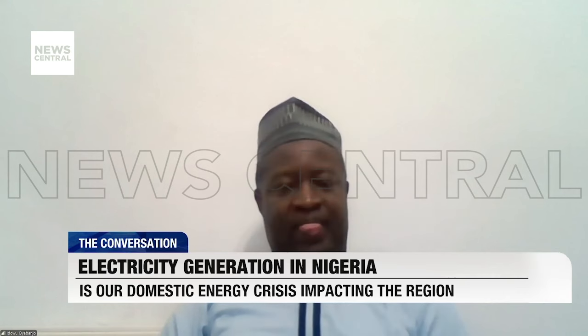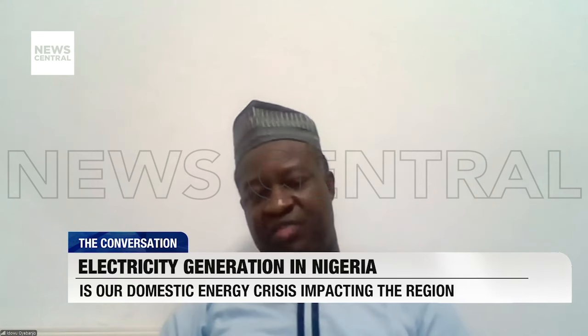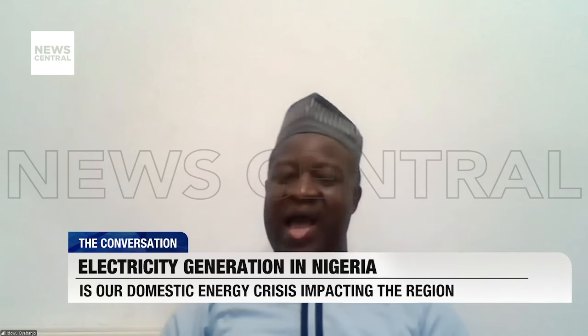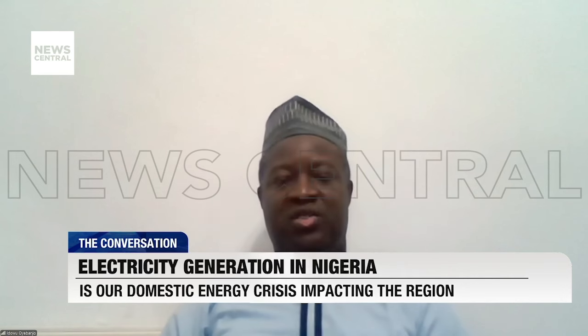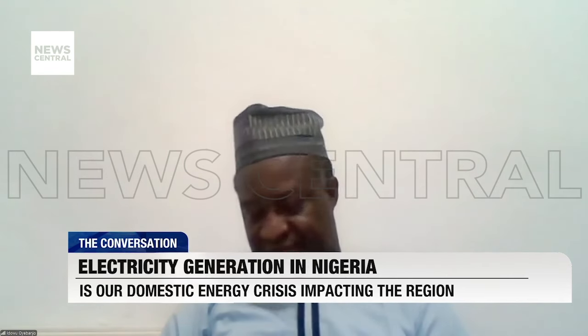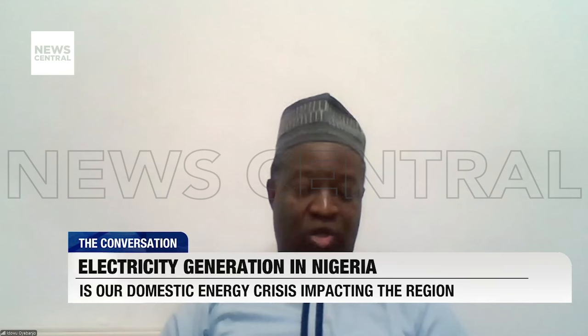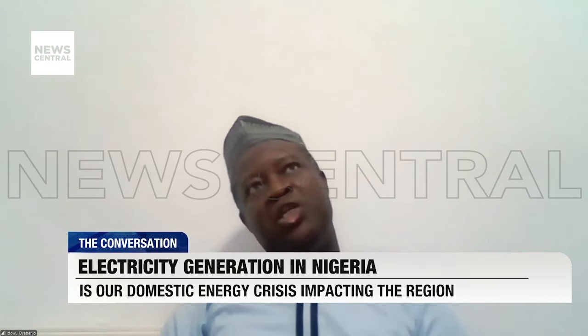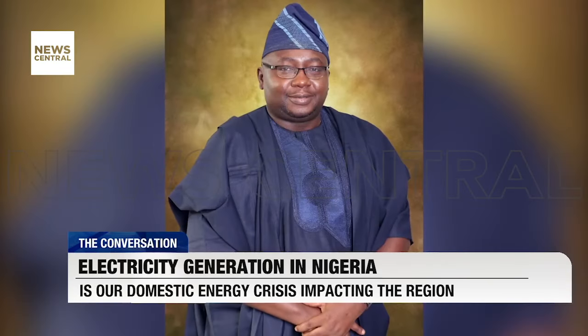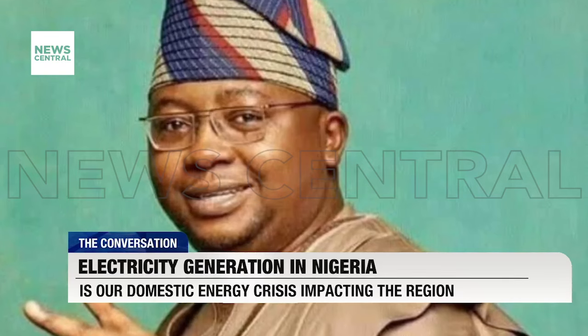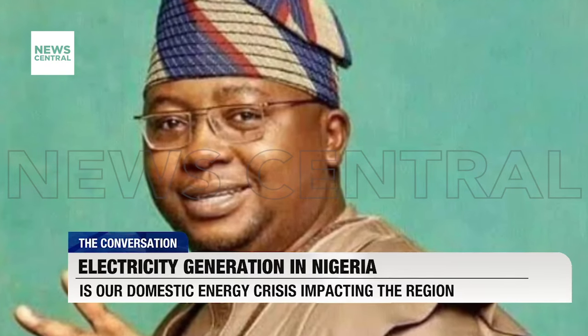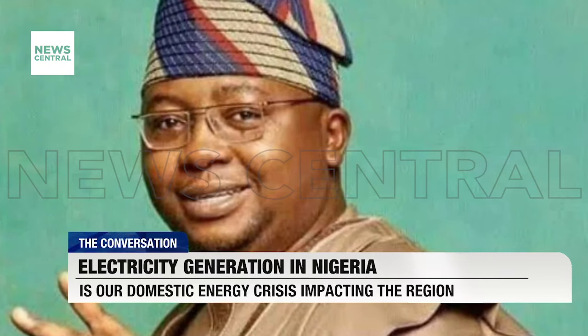Okay, so I've just given you one reason why you have grid collapse. Another important reason, which is the one that happened on Saturday, the one you called the third grid collapse, is protection. The Nigerian power system lacks adequate protection systems that are well coordinated, and it will continue to trip around 5,800 to 6,000 megawatts. You are going to witness a lot of tripping and grid collapse.